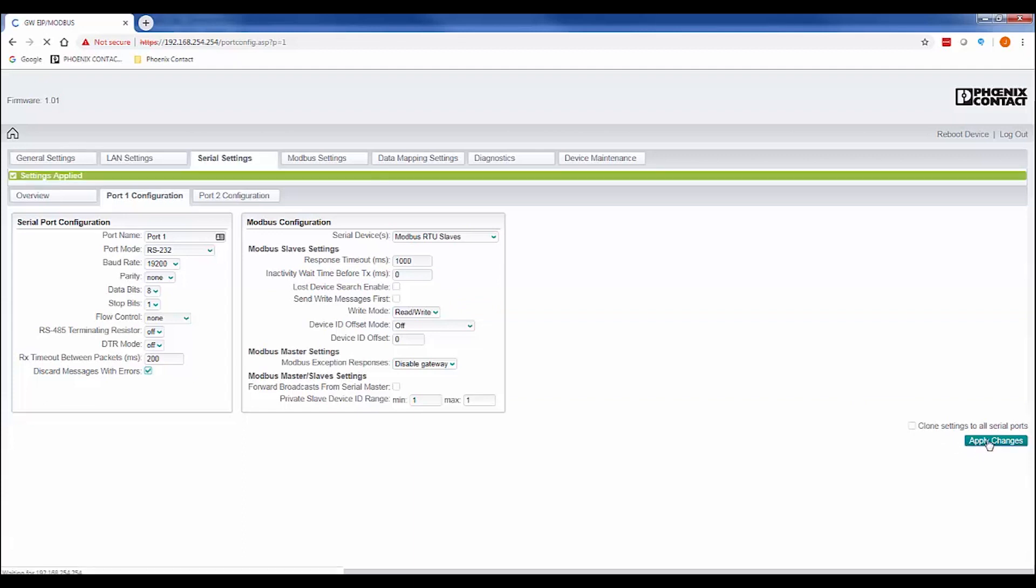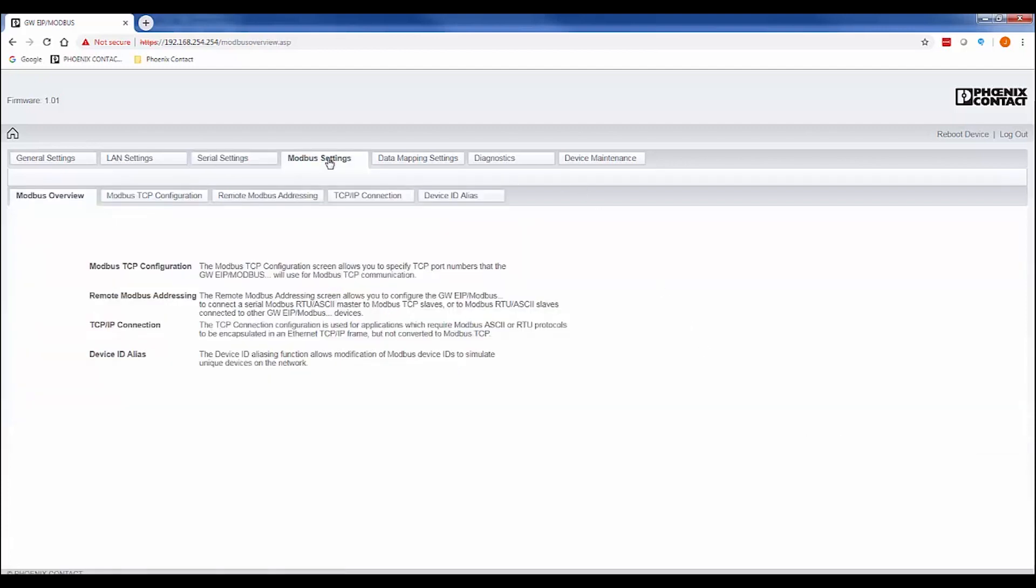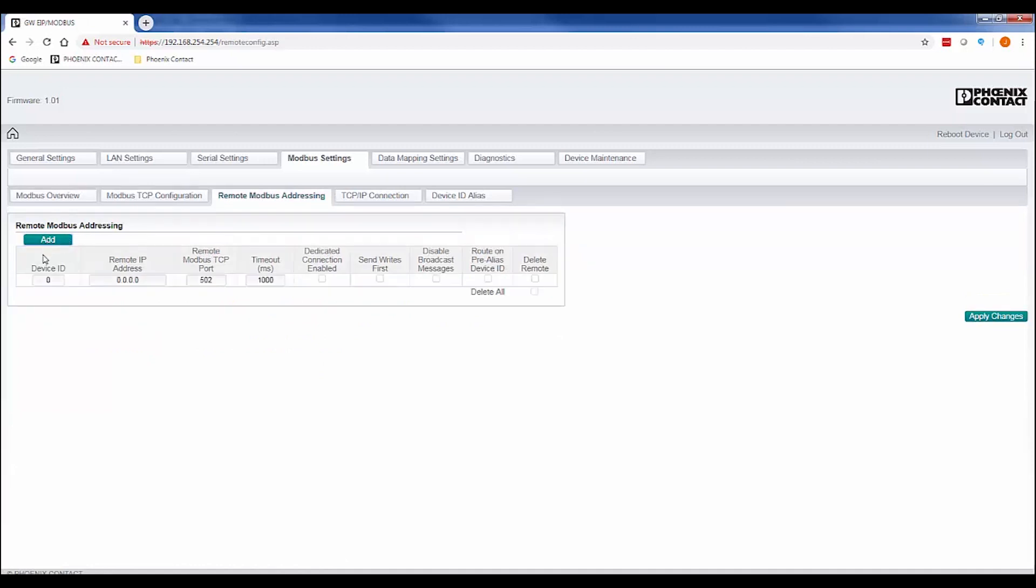This completes the configuration for your Modbus RTU device. Click the Apply Changes button and move on to set up the Modbus TCP communications to our second slave. Select Modbus settings, then the Remote Modbus Addressing tab. Click the Add button and enter the device ID that will be associated with your Modbus calls. For this example, we'll enter 3 and then enter the IP address of the Modbus TCP device we want to gather data from, then click the Apply Changes button.